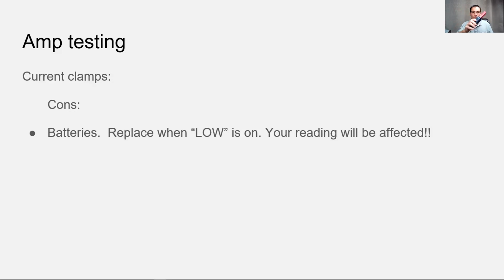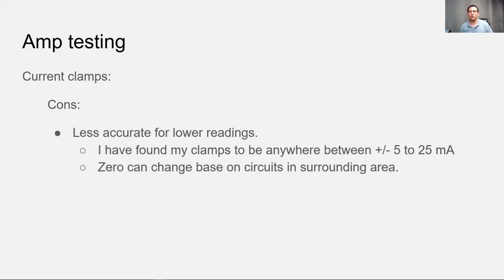Also, the drawbacks of the current clamp are the batteries - if the battery's going dead as you're testing, which I've had happen, you get bad readings. And also the zero - you can hit zero, but when you move that amp clamp around, you will get different readings depending on the angle you hold it at. So it's not super accurate.